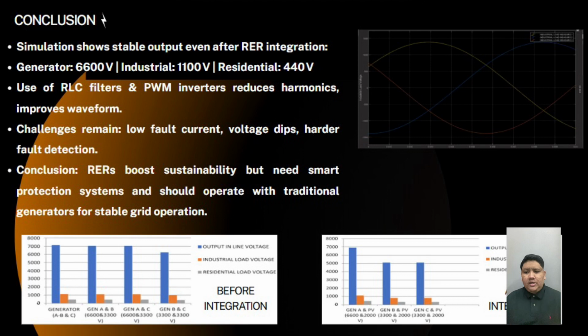However, the integration of renewable energy also introduced new protection challenges. Since solar PV systems produce low fault current and are connected through inverters, it becomes harder to detect and isolate faults quickly. Issues like voltage flicker, harmonic distortion, and reduced system inertia highlight the need for more adaptive protection mechanisms such as real-time monitoring, intelligent relays, and smart coordination strategies.